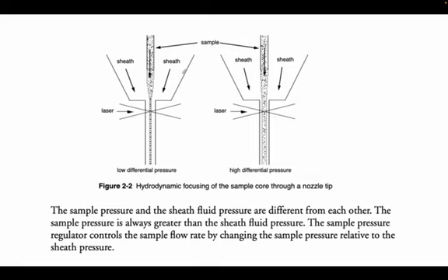So hydrodynamic focusing basically requires a difference in pressure between the sheath fluid and the sample fluid. If we have low differential pressure, then it will be focused well. If we have high differential pressure, then we will lose the sample focusing.